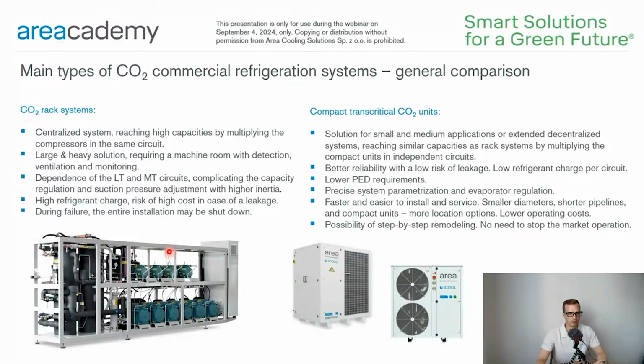Another solution are compact transcritical CO2 units. This solution is dedicated for small and medium applications or extended decentralized systems, reaching similar capacities as rack systems by multiplying the compact units in independent circuits. This results in better reliability with a low risk of leakage. In such systems, the refrigerant charge per circuit is much lower than in rack systems. Also, the PED requirements are lower.